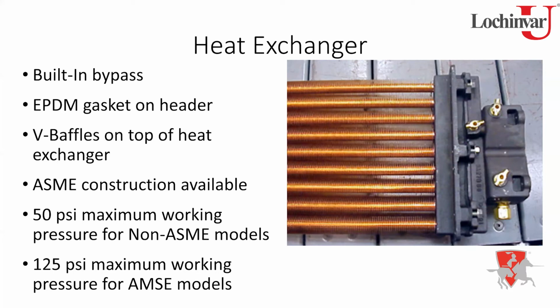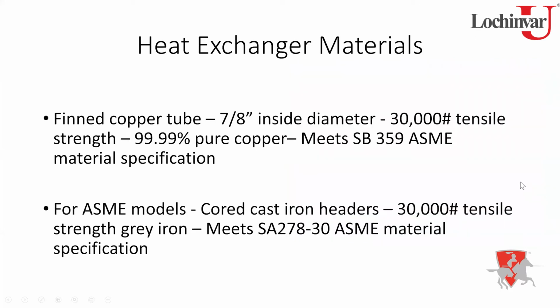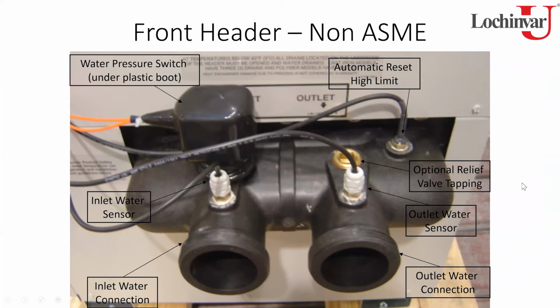As your water comes into the heat exchanger, I'm going to go over here to another slide. Skip that, real quick. Here's our front header for our non-ASME. If I look at my inlet water as it comes in on this left side, only a certain amount of that water is actually going to go down through the tubes. The rest of it is going to be bypassed. Whether I'm bypassing 10 GPM or 50 GPM, I'm bypassing a certain amount. Only a little bit of water is actually going to go down through the heat exchanger tubes.